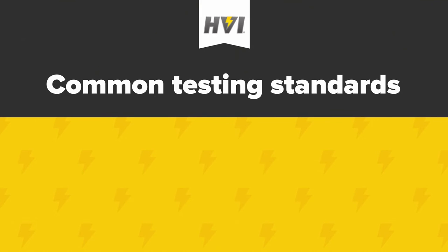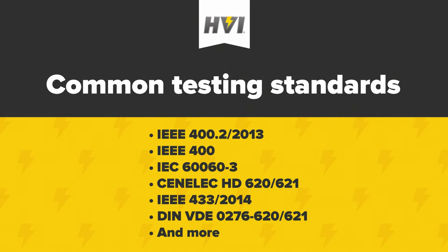HVI's VLF E-Series are advanced VLF, or very low frequency AC HIPOTs, used for the testing of high voltage cables and motors or generators. Common testing standards that the VLF E-Series support include IEEE 400.2 2013, IEEE 400, IEC 60060-3, Cenelec HD 620-621, IEEE 433-2014 for motors or generators, and many other local standards.